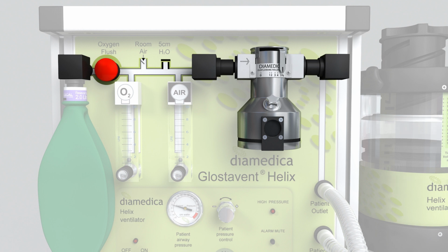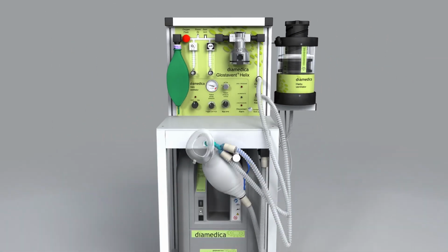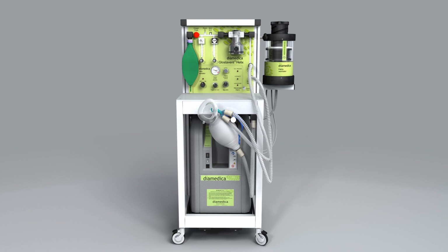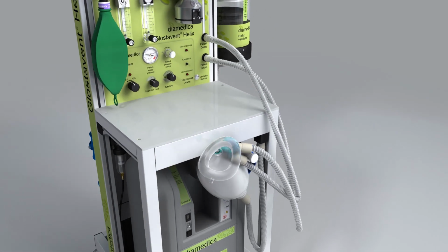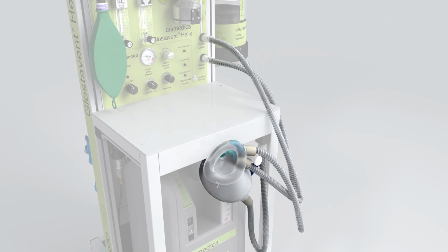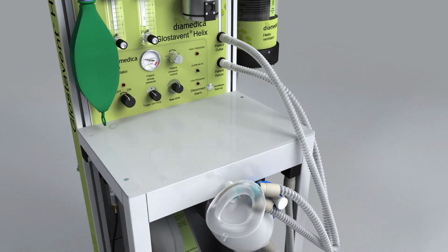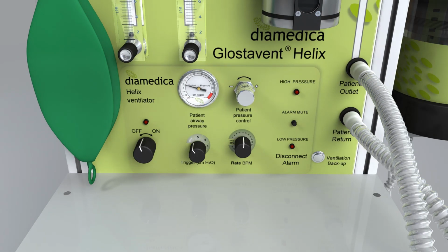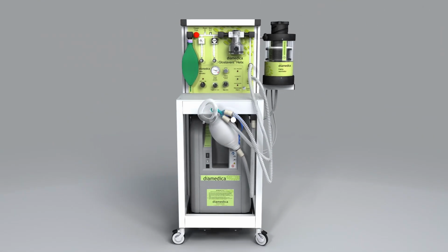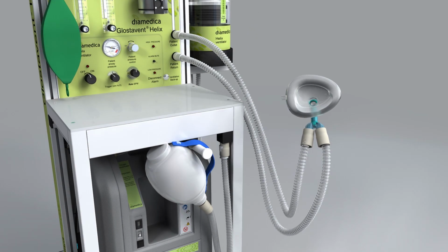In draw-over mode, room air is drawn in here, over the vaporizer, through the ventilator, and out to the patient. You can add supplementary oxygen to this room air to increase the FiO2. If more gas is put into the system than the patient's minute volume, the reservoir bag will fill and an increase in pressure will turn the system into continuous flow. The normal patient circuit is an open circuit through a standard 2-limb autoclavable tube. The patient non-rebreathing valves are located in the control panel. An adult and pediatric circuit are provided as standard. The end of the circuit can be fitted directly to a mask or ET tube.